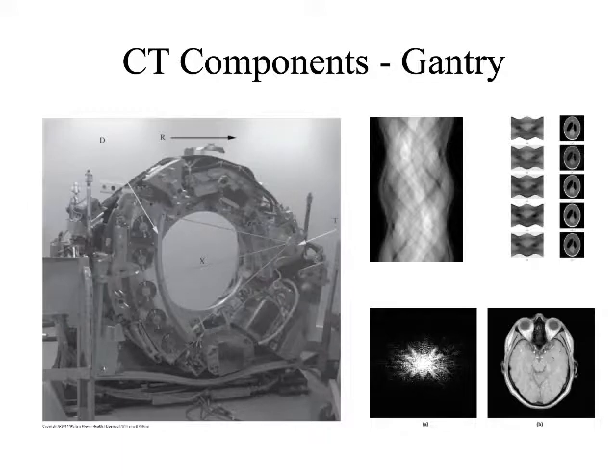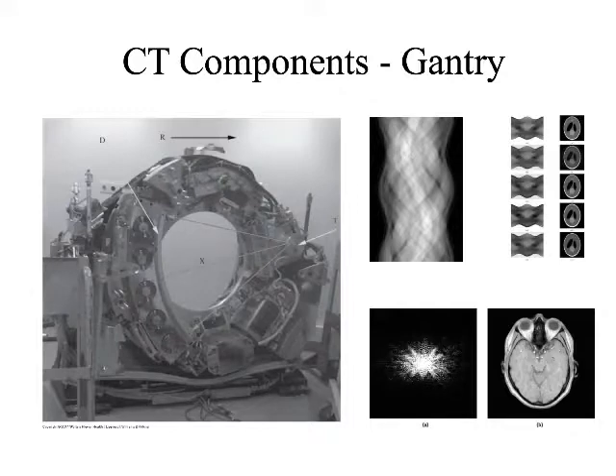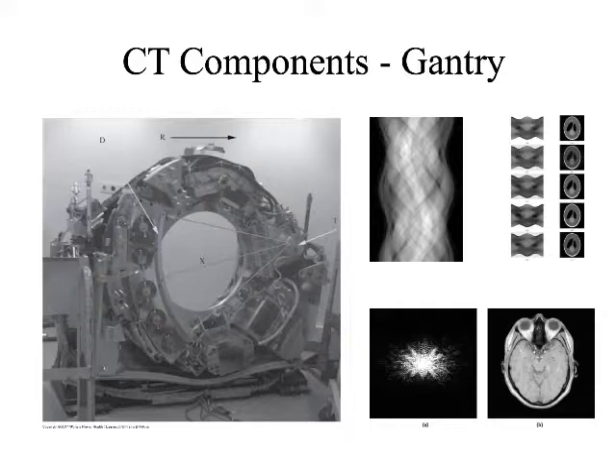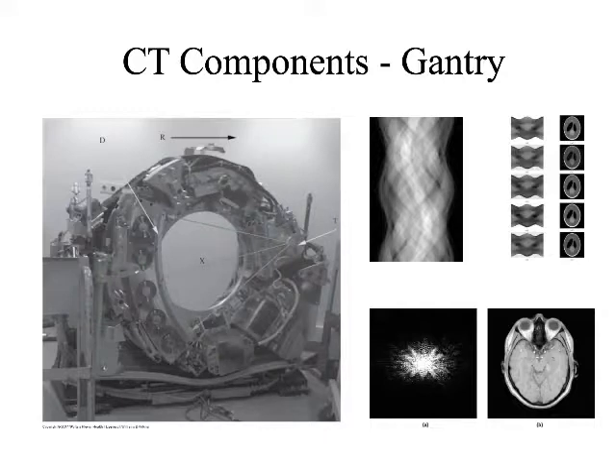The geometry of the x-ray beam is important. We primarily use cone beam geometry — the x-ray beam is shaped like a cone — which is also used for image acquisition in radiation therapy. The point at the center of the gantry, around which everything rotates, is called the isocenter. The CT scanner's isocenter is not to be confused with the linear accelerator's isocenter, though they serve a similar purpose.